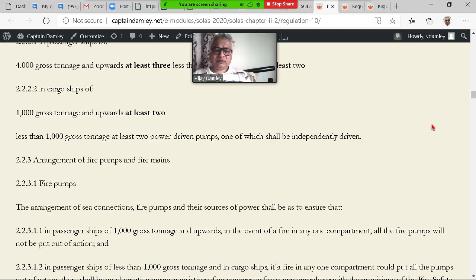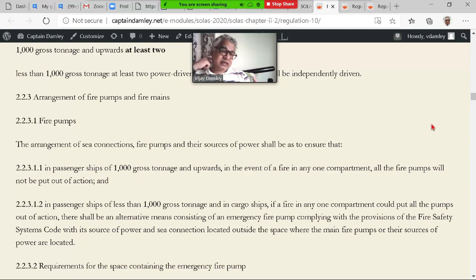So what happens is there is a remote arrangement, and again, that first part we saw, always readily available 24/7. Just press the button, the pump starts, and within a few seconds water will be there at the hydrant. A few seconds, I am not going to say even minutes, because ashore it happens very often that they don't realize the amount of water required to fill up the pipeline, and then it needs 10 minutes to fill up the pipeline, and only after 10 minutes you will get water. That is not acceptable.